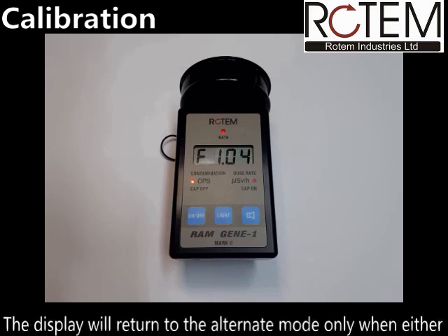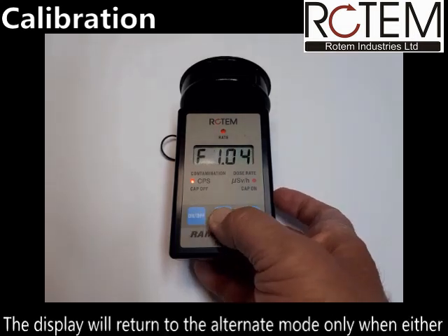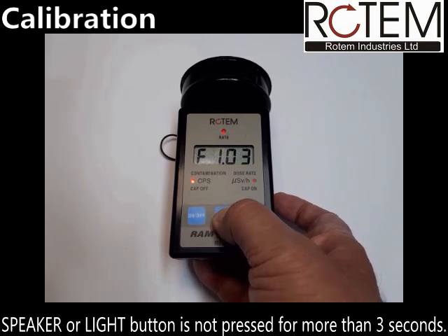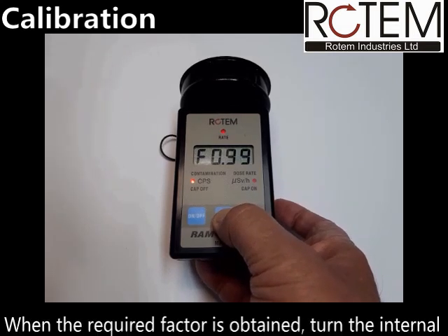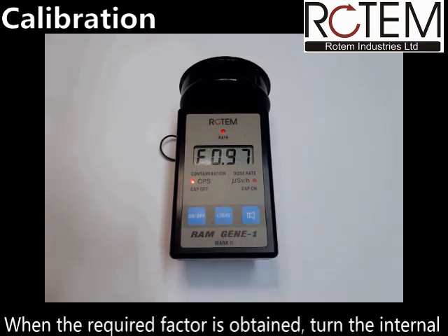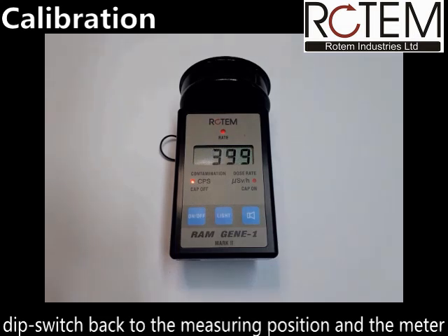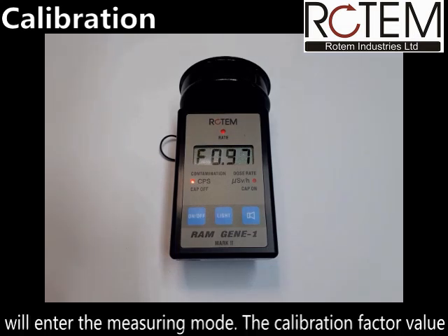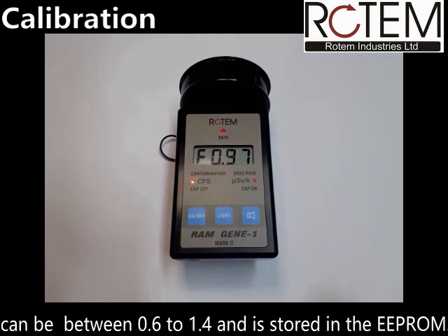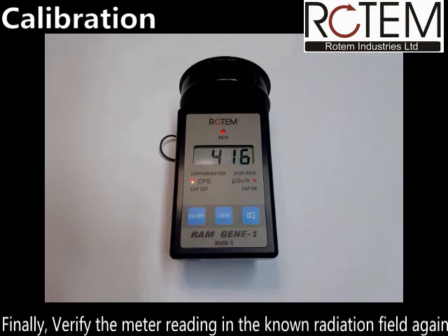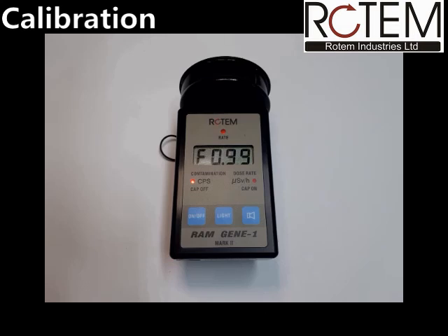The display will return to the alternate mode only when either speaker or light button is not pressed for more than 3 seconds. When the required factor is obtained, turn the internal dip switch back to the measuring position and the meter will enter the measuring mode. The calibration factor value can be between 0.6 to 1.4 and is stored in the EEPROM. Finally, verify the meter reading in the known radiation field again.